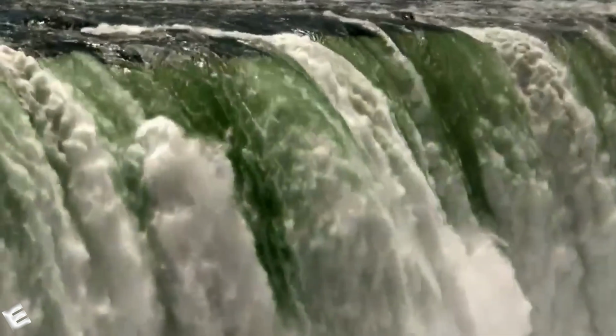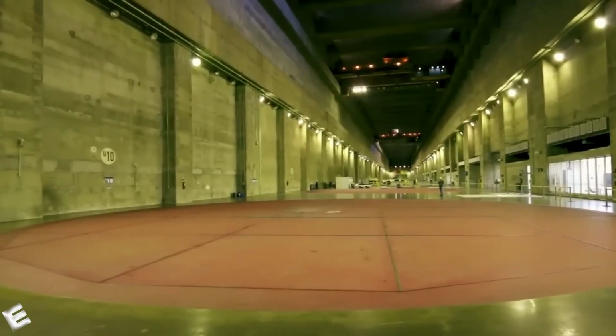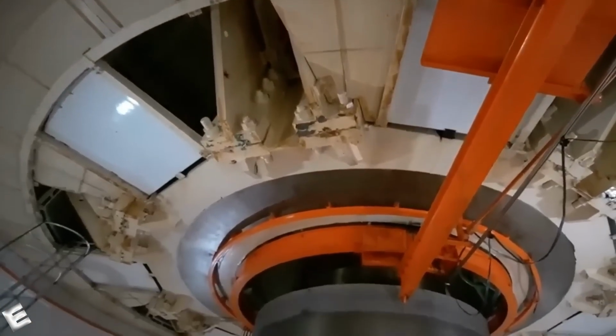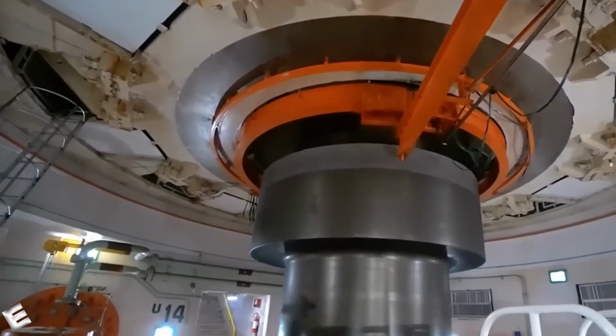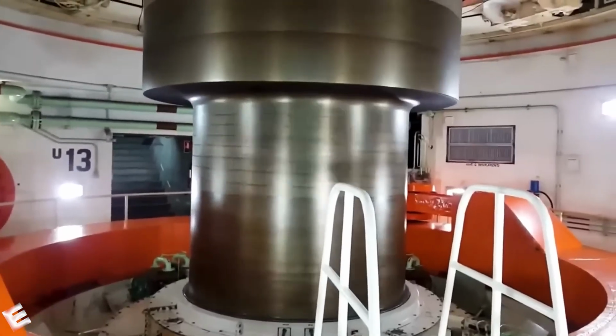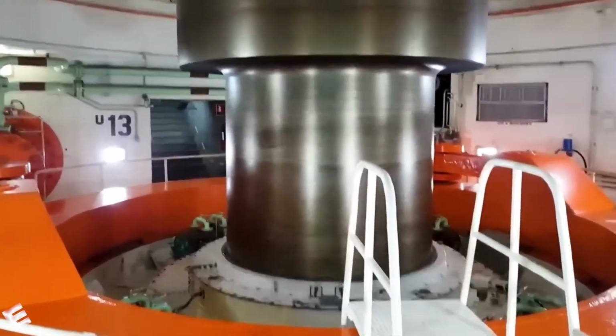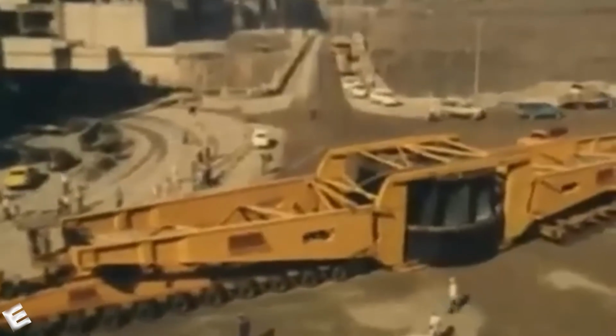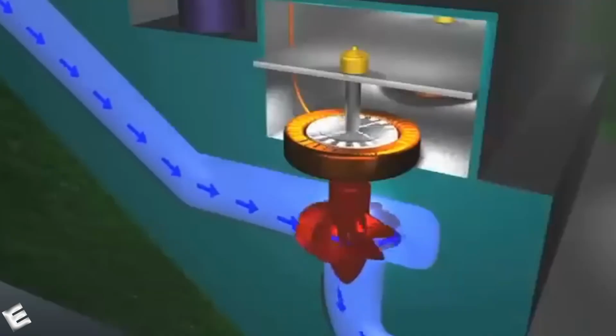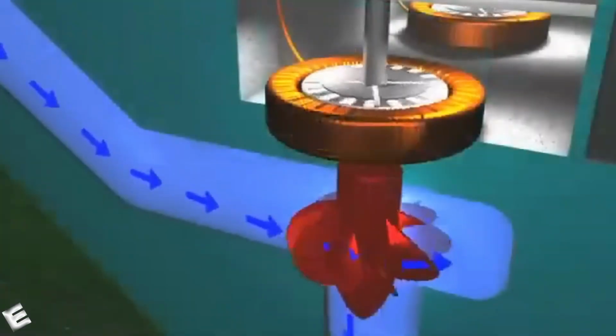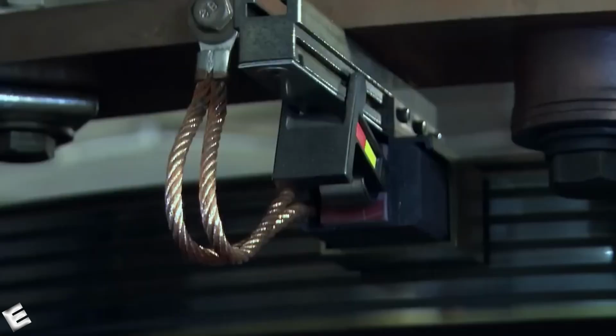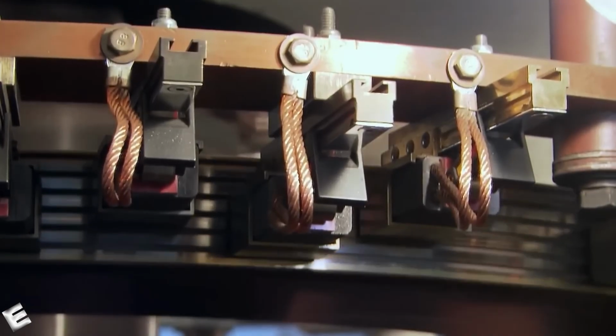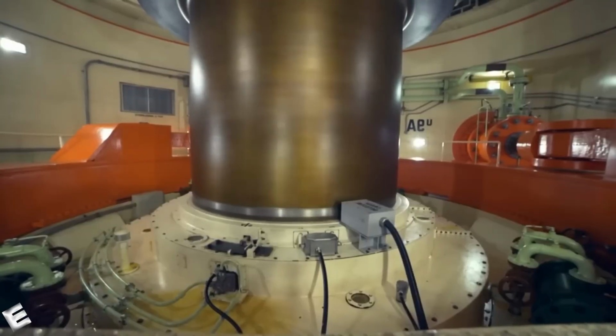Meanwhile, inside the hydroelectric plant, a gigantic underground installation houses the enormous turbines and generators responsible for transforming the energy of water into electricity. Each unit reaches approximately 88 feet in height and weighs close to 6,600 tons. They are so colossal that special transportation systems had to be designed to move and install them inside the plant. At the heart of each turbine is the rotor, one of the most important pieces in the entire system. Its job is to spin powerful magnets inside copper coils, allowing electricity to be generated through electromagnetic induction. Although these rotors are more than 52 feet in diameter, they must be installed with extreme precision, with tolerances of less than 1/10 of a millimeter. Even the smallest error could affect the performance of the entire system.